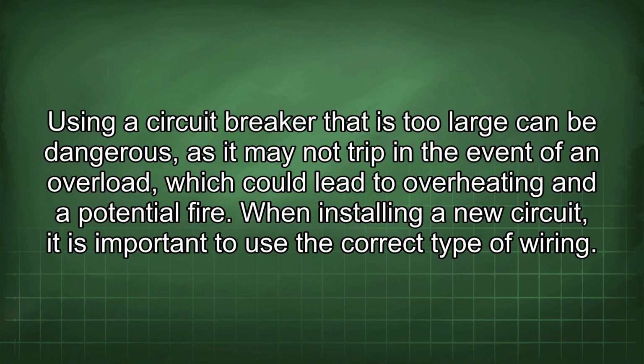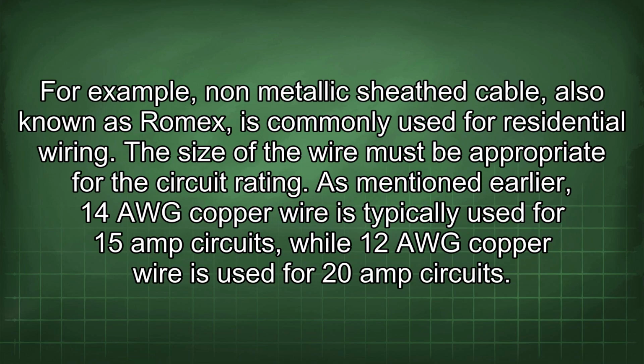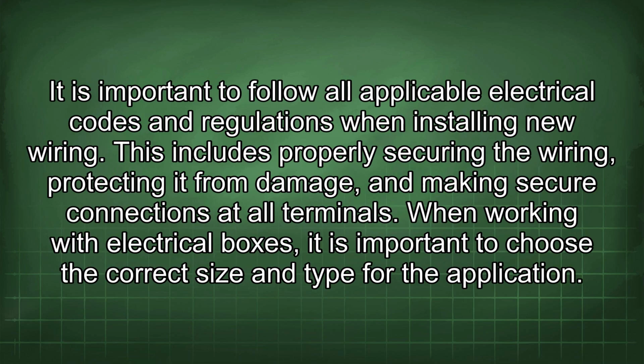When installing a new circuit, it is important to use the correct type of wiring. For example, non-metallic sheath cable, also known as Romex, is commonly used for residential wiring. The size of the wire must be appropriate for the circuit rating. As mentioned earlier, 14 AWG copper wire is typically used for 15-amp circuits, while 12 AWG copper wire is used for 20-amp circuits. It is important to follow all applicable electrical codes and regulations when installing new wiring. This includes properly securing the wiring, protecting it from damage, and making secure connections at all terminals.